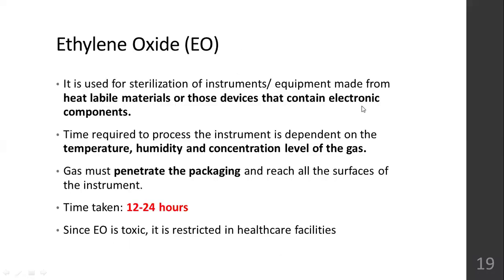Then you have ethylene oxide, EO plant. That is used for sterilization of instruments or equipment made from heat-labile materials, or those devices that contain electronic components. So any equipment or instrument which has inbuilt batteries or any circuits inside it, for that, ethylene oxide is ideal. Time required to process the instrument is dependent on the temperature, humidity, and concentration level of gas. If the concentration level of gas is very high, sterilization can be achieved in a very short time. But if the concentration of the gas is very low, you need more time for the sterilization to be achieved. And this ethylene oxide gas should penetrate each and every part of the packaging. Otherwise, it is not adequately sterilized.